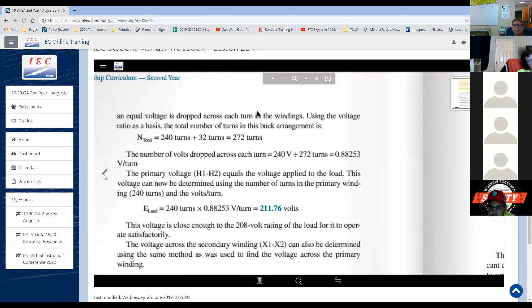and 208. These two numbers are close enough, right? 3 volts ain't enough to cause a big uproar. So that's good. And that was because at 240 volts, we had those extra turns, 240 plus the 32 turns. We actually ended up with a reduction, a buck transformer. That's a long explanation to it.